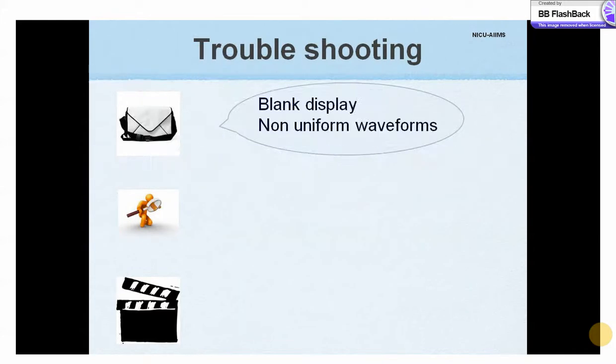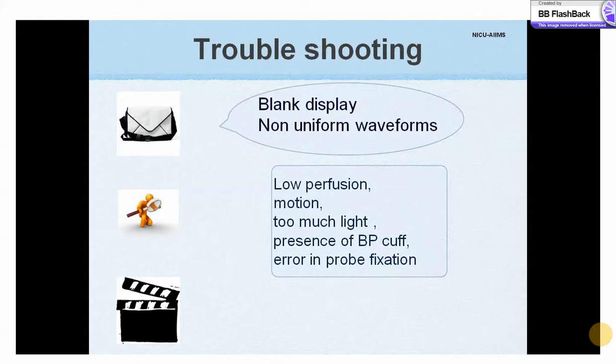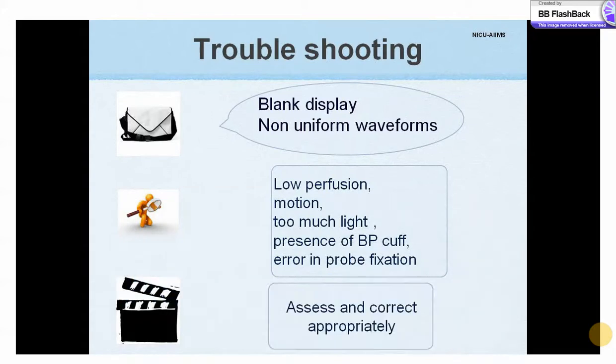In case of a blank display or non-uniform waveforms, the causes could be many — including low perfusion, motion, too much light, presence of a BP cuff on the arm, or simply an error in probe fixation. The actual cause should be actively searched for and corrected accordingly.